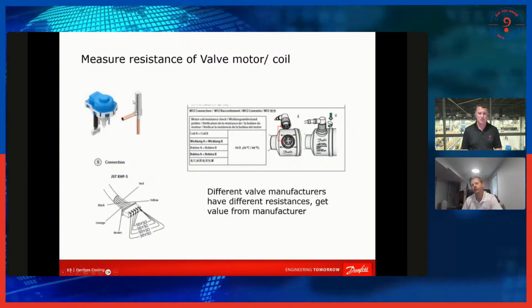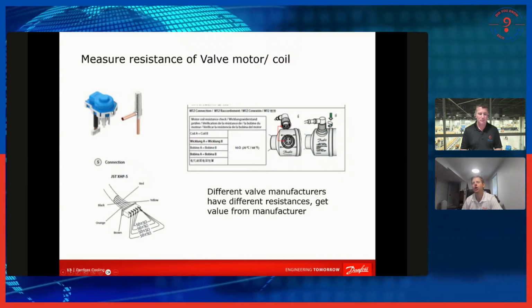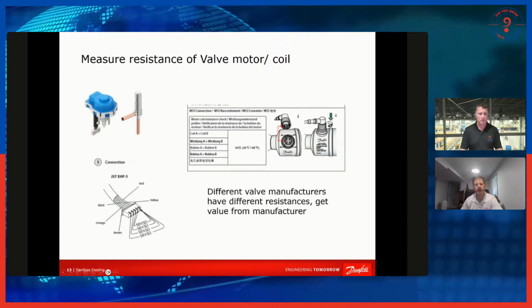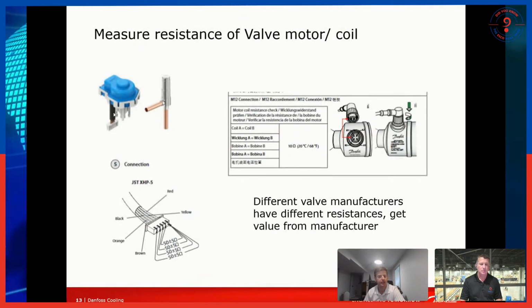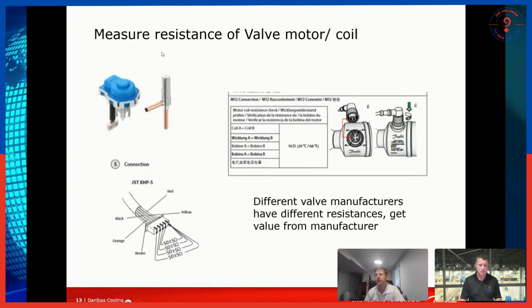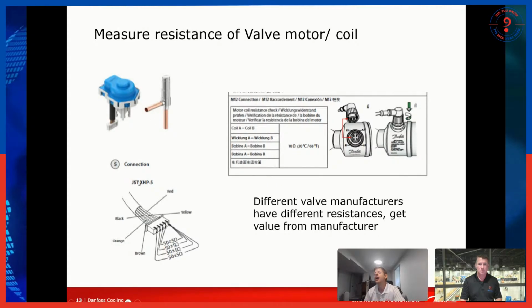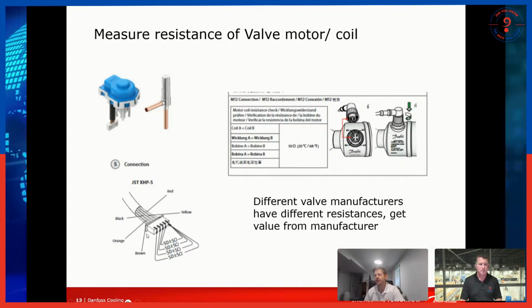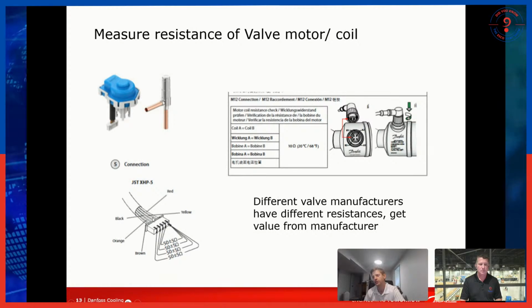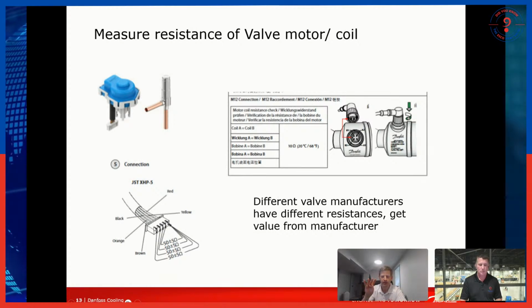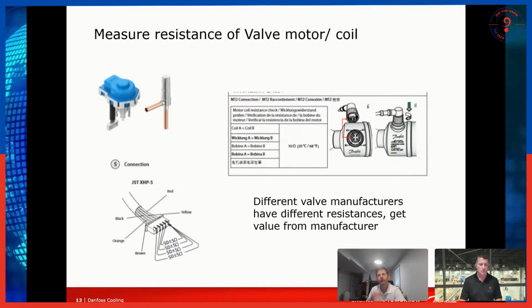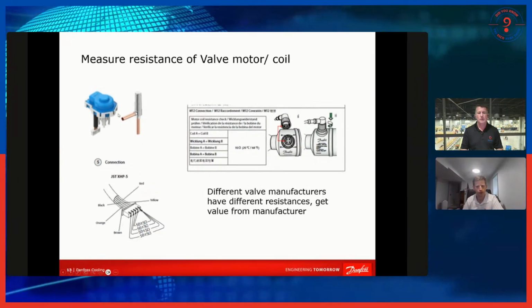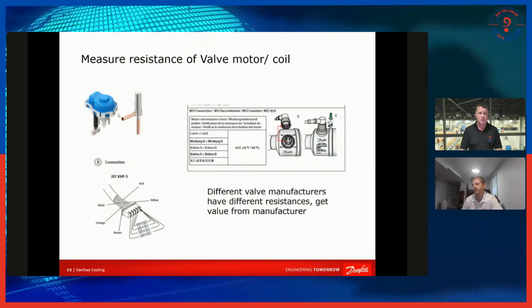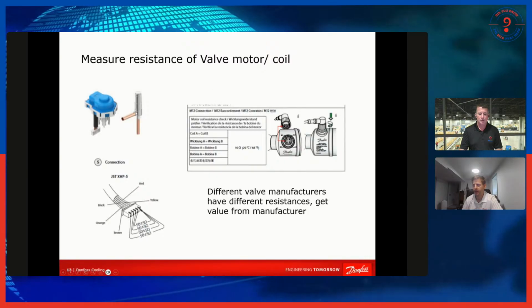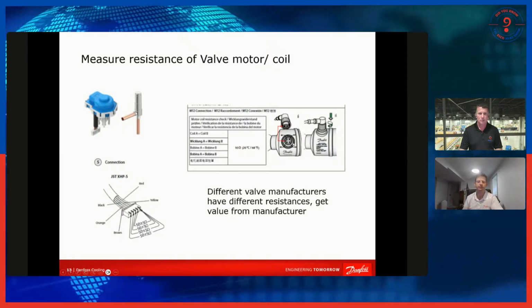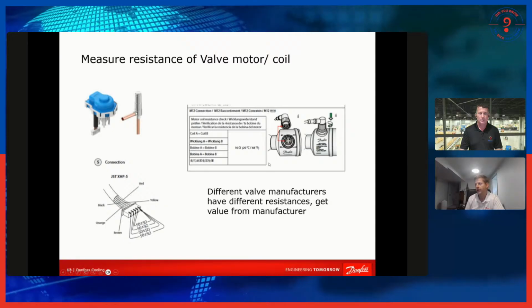The unipolar stepper motors tend to be in these smaller EXVs. They're very popular in VRF and residential HVAC systems. Generally small capacity, single-digit tonnages. One of the main ways you can identify them is that they will have 5 or 6 wires on them, because there'll be 4 wires that get power and then either 1 or 2 wires that are a neutral. And that's a unipolar valve, a different type of design. And then there's the bipolar valves that are typically larger EXVs, and there will just be 4 wires there.